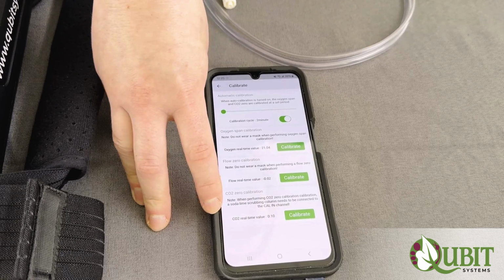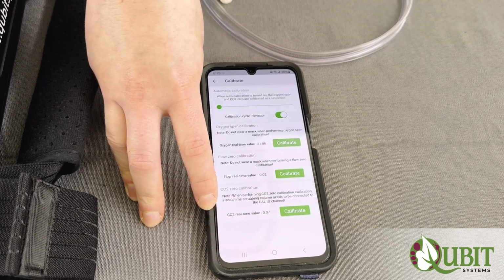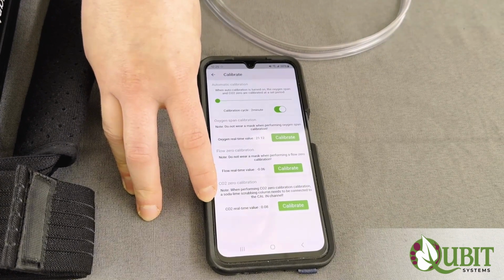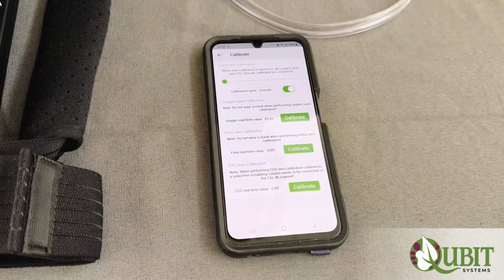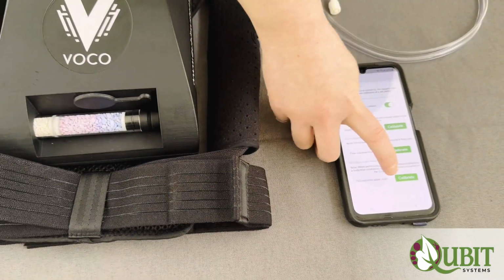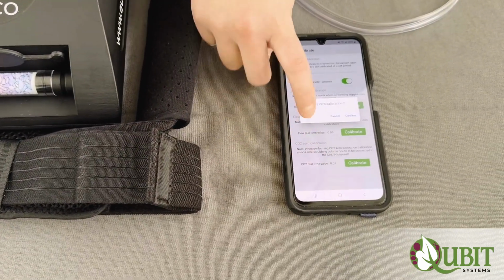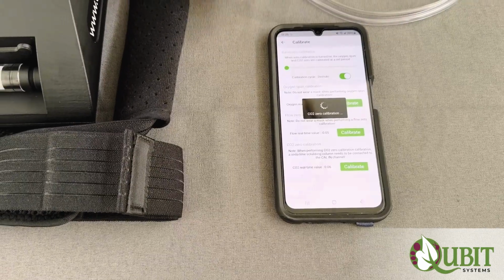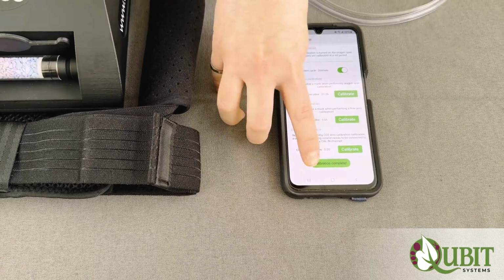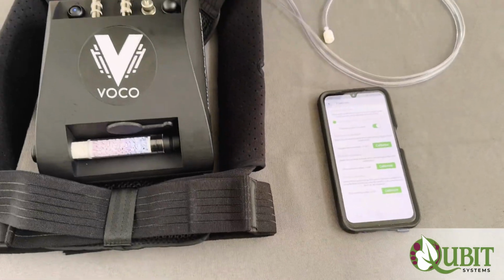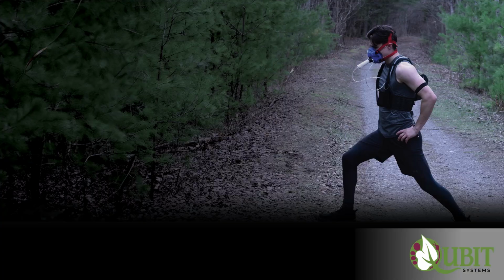Finally is the CO2 zero calibration. And again, during this particular calibration, the VOCO will be pulling from the VOCO calibration column. So again, we hit calibrate, confirm, and the calibration is complete. The VOCO is now calibrated and ready to use.